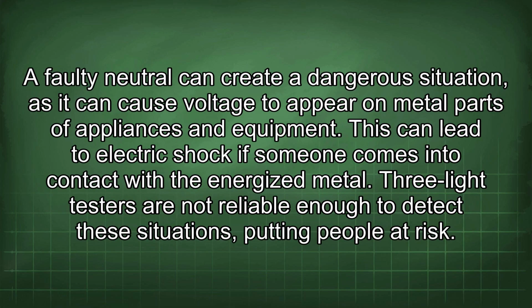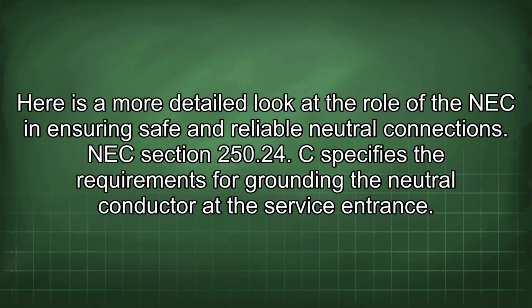A faulty neutral can create a dangerous situation, as it can cause voltage to appear on metal parts of appliances and equipment. This can lead to electric shock if someone comes into contact with the energized metal. 3-light testers are not reliable enough to detect these situations, putting people at risk. Here is a more detailed look at the role of the NEC in ensuring safe and reliable neutral connections.